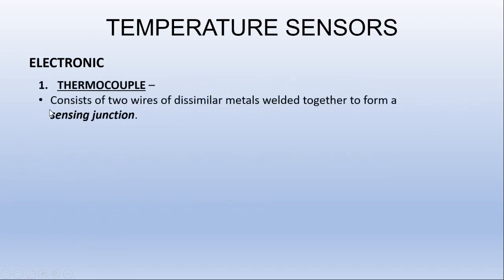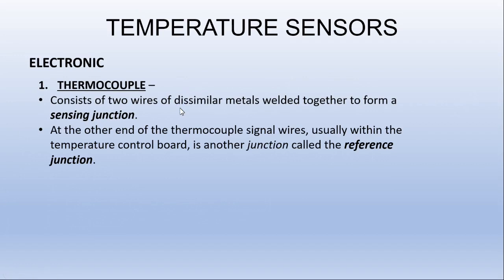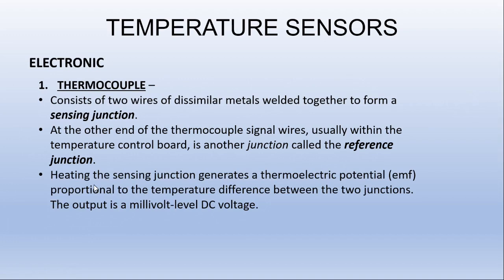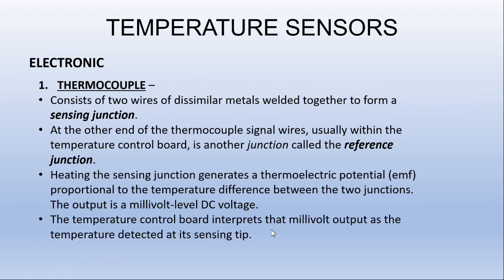The thermocouple consists of two wires of dissimilar metals welded together to form a sensing junction. At the other end of the thermocouple signal wires, usually within the temperature control board, is another junction called a reference junction. Heating the sensing junction generates a thermoelectric potential, or electromotive force, EMF, proportional to the temperature difference between the two junctions. The output is a millivolt level DC voltage. The temperature control board interprets that millivolt output as a temperature detected at its sensing tip.